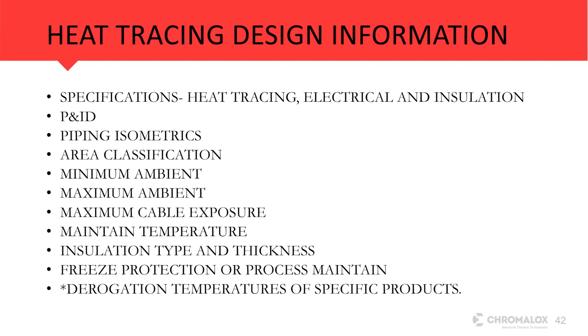And one other thing I like to mention is the degradation of temperatures of specific products. So sometimes when we go and do a heat tracing project, we run into issues where certain products cannot go over a certain temperature. So if you do have those cases, it's best to let us know that up front so that we don't degrade product by overheating it, or we can shut it down before it gets to those temperatures. Those are the kind of things that we need to know and we need to look at up front whenever we're doing a heat tracing design.